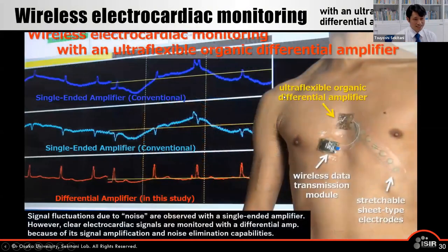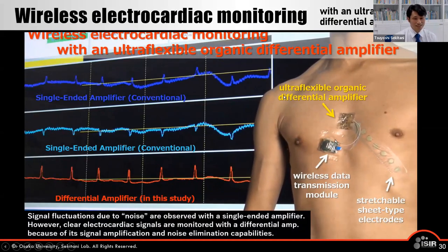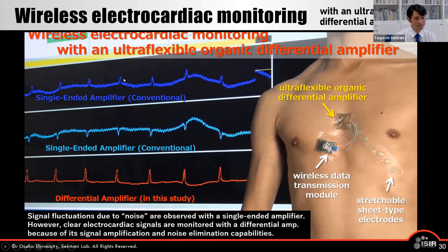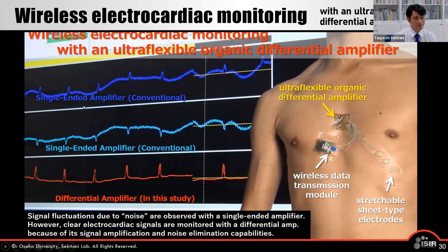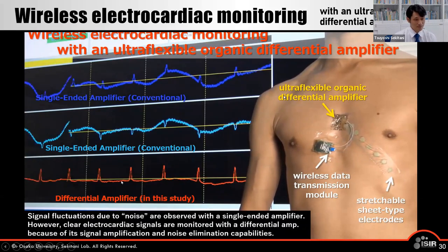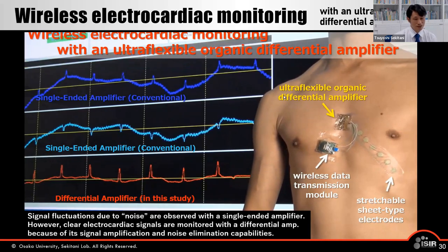This movie shows ECG monitoring that integrates a stretchable electrode, ultra-thin differential amplifier, thin-film battery, and wireless communication module. The upper two ECG signals in blue and light blue were measured without the use of the differential amplifier circuit — the baseline is largely fluctuated and very noisy. The bottom ECG in red line shows the signal where noise and baseline fluctuations have been removed by our differential pair amplifiers. You can see how little noise there is using the thin-film differential amplifier — disturbance noise artifacts can be significantly reduced.